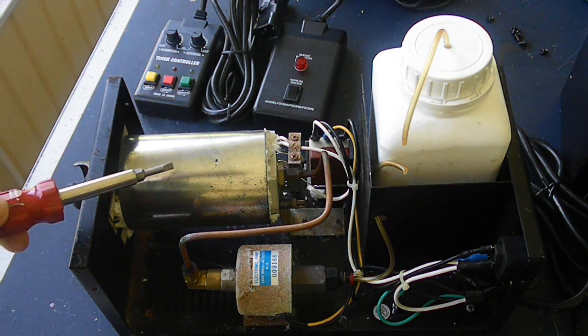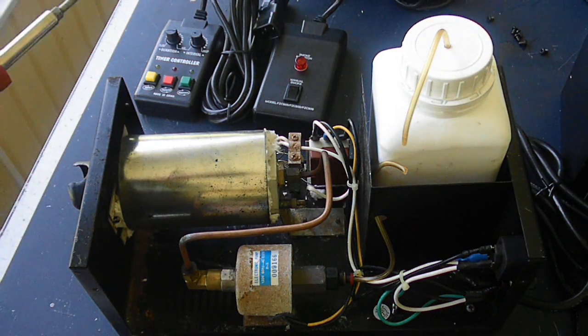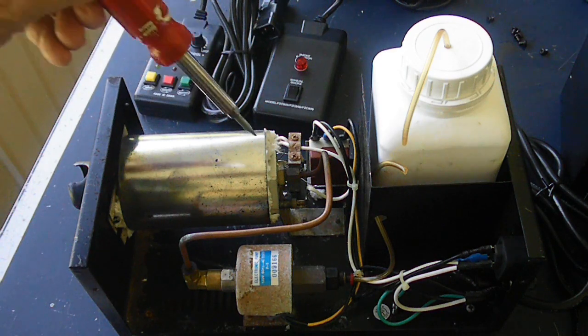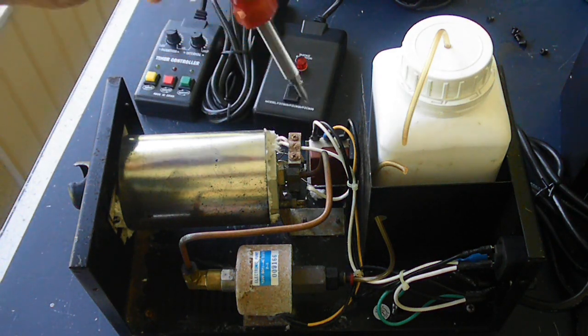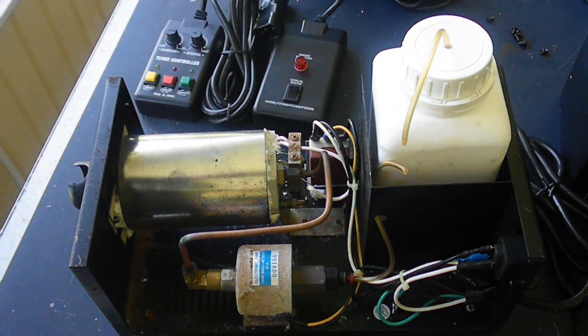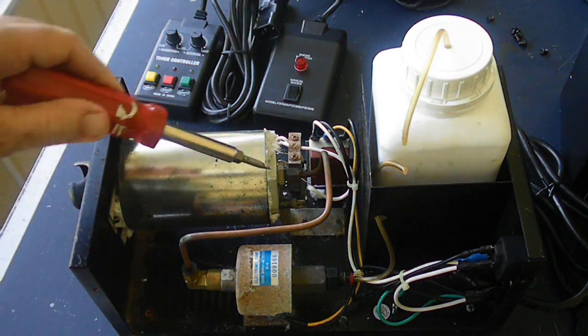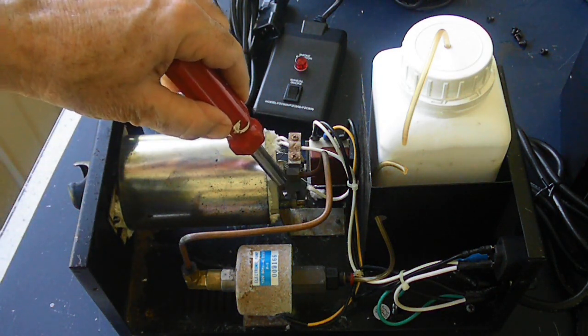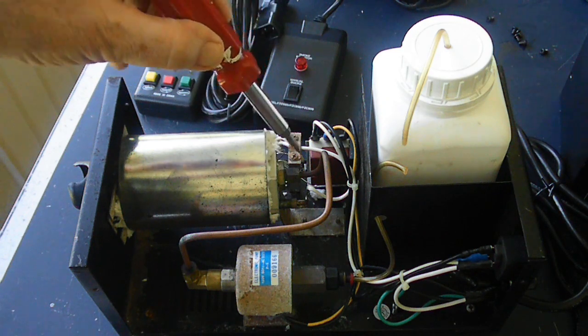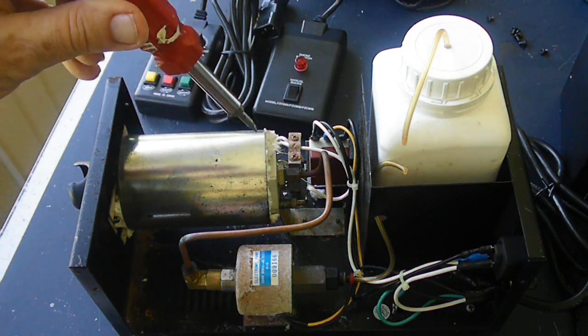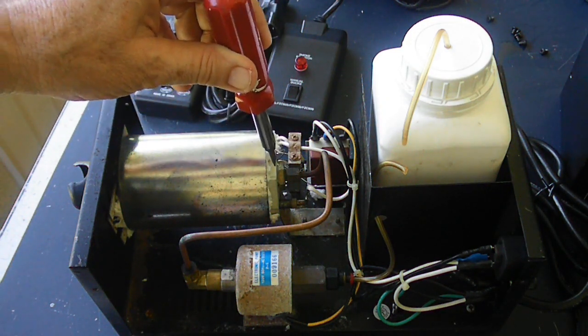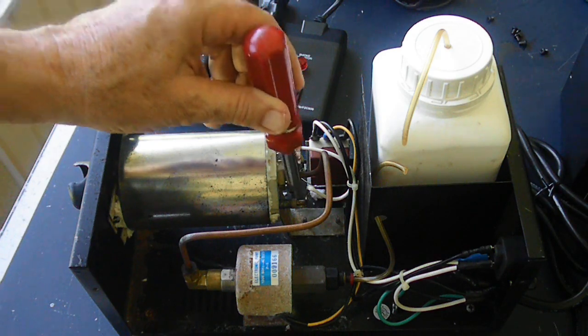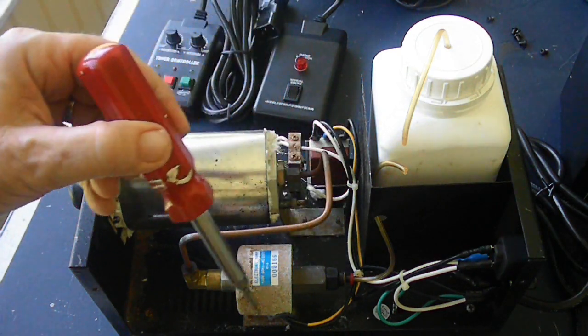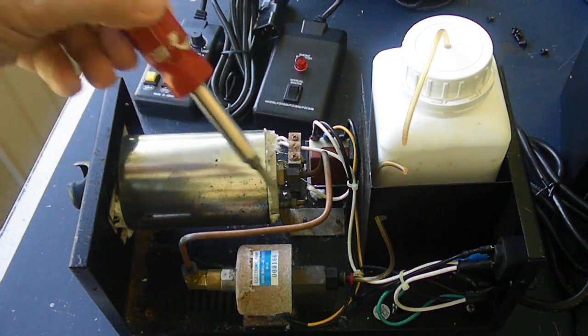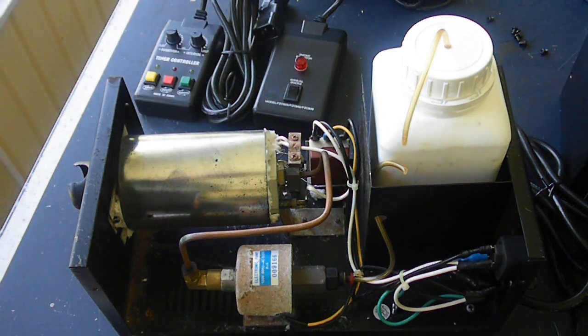Less elaborate, simpler and newer machines have replaced this thermocouple with just a click switch on the block. The heaters will basically steal all the power from the unit while they're running. This click switch, when it gets to temperature, will open up, turning off the heaters, and the power then becomes available so your pump can be run.